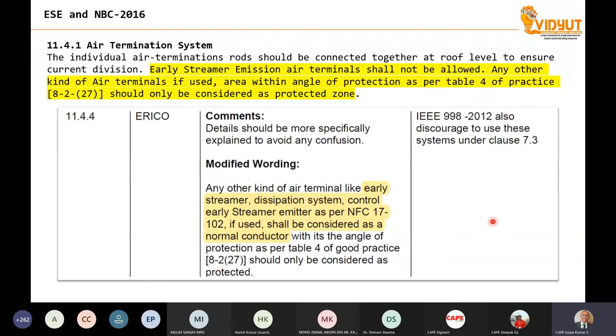What they recommended is modified wording: any other kind of air terminal like early streamer dissipation system, controlled early streamer emitter as per NFC 17102, if used, shall be considered as a normal conductor. So he is trying to make it more specific. He says if these ESE and other things as per the French standard are used, then it has to be considered as a normal rod only. This is what he has written. His comment also noted that IEEE discouraged the use of this system under clause 7.3.